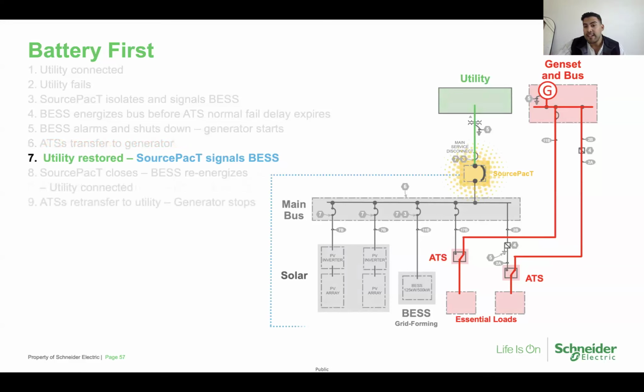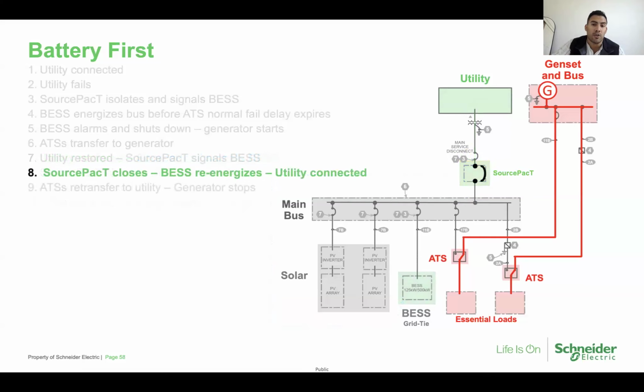SourcePacT will now detect that utility has been restored. So this could be like an 8-hour-long outage. Once we detect that utility is restored, we'll send a signal to the battery energy storage system telling them we're about to enter a grid tied operating mode. The breaker will now close. The battery energy storage system and the PV inverters will sense that the main bus is energized, so the PV and energy storage system will come back online.